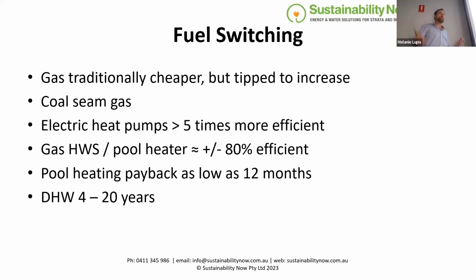But even so, you still get a decent return on investment replacing a big centralized gas hot water system with a heat pump system. It depends on the actual building, because they're a bit trickier to install - they need more space, they're bigger, need better airflow, and a decent electricity supply. So there are barriers, but I've seen payback periods as low as 3 years on very small buildings, maybe 5 years, or 5 to 10 years on a bigger building.